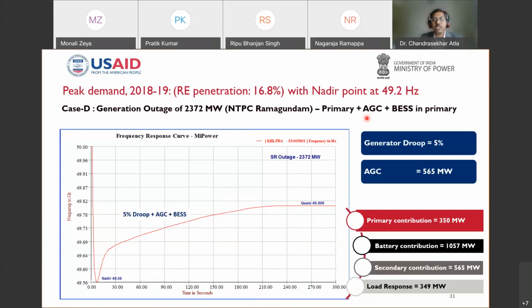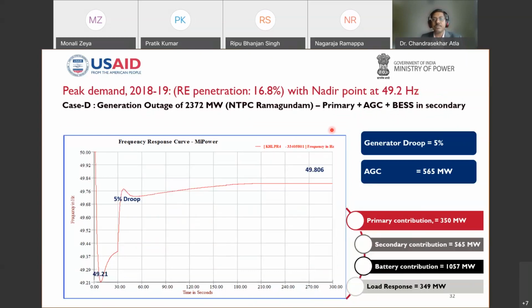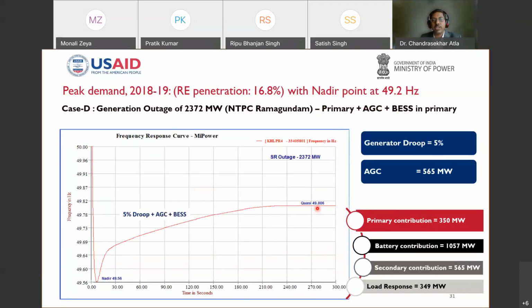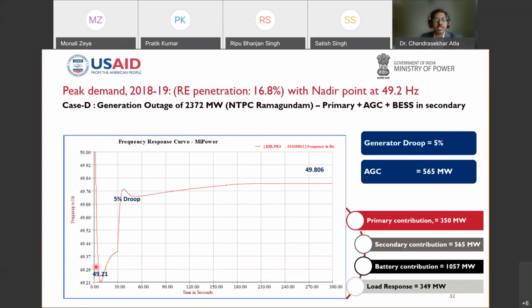Taking that into consideration, we will now see one more case where the BES participates not in primary but in secondary. So now we deploy primary and AGC from the conventional units, but BES only in the secondary. Because BES is not entering the primary control, frequency falls to 49.2 like the earlier case, but after 30 seconds the secondary reserves start deploying in the system, and frequency gets fixed up. The settling frequency, or quasi steady state frequency, is 49.8 like the previous case, but the nadir frequency, because of the absence of BES, was not much improved. That means I have not improved the stability of the system much, but I managed to settle the frequency. So, from the simulation studies, we also drew some conclusions.